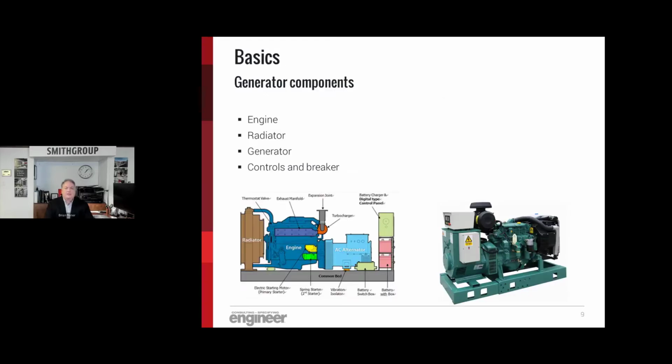So let's first talk about the components in the generators. We call them generators, but really there are both primarily an engine and a generator component. There's a radiator and there's controls and breakers. These are important to understand because although from the vendors you will get a standard package, it is possible to consider different engines and different generator changes when you're specifying engine and generators. So this will help you get an idea of where the components are.